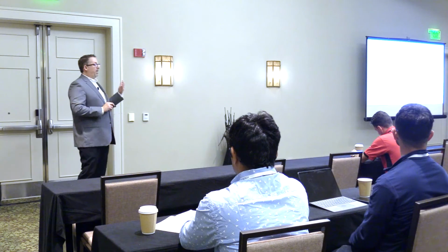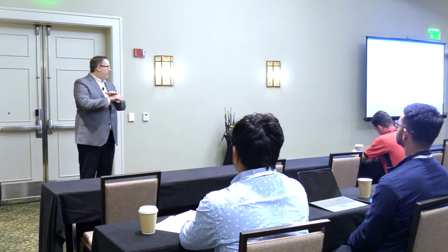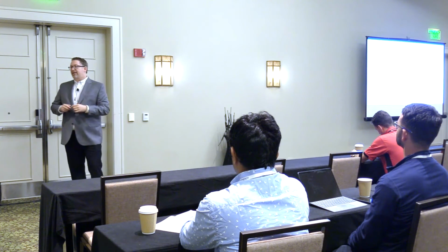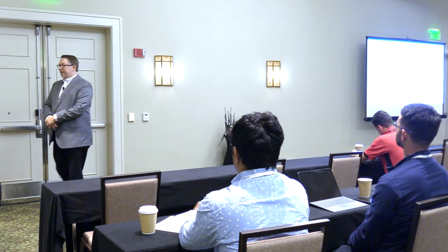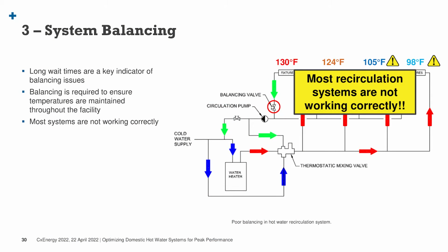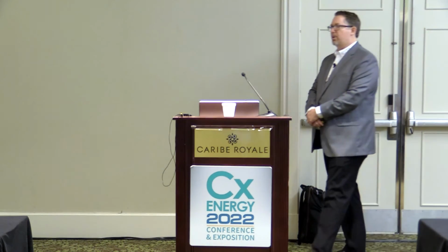Again, a lot of times when you get into an existing building, you turn it over, it's been a set it and forget it for the owner. They don't maintain those valves, they neglect it, they have renovations or repairs and they don't go back and check the balancing of the system or how that impacted the balancing of the system. And again, neglected maintenance. And bottom line is most existing balancing systems are having issues. And a lot of times what'll happen is we just adjust our behavior, right? If it takes a long time for hot water, we just let it run longer, instead of actually addressing or trying to identify that key source of the problem.